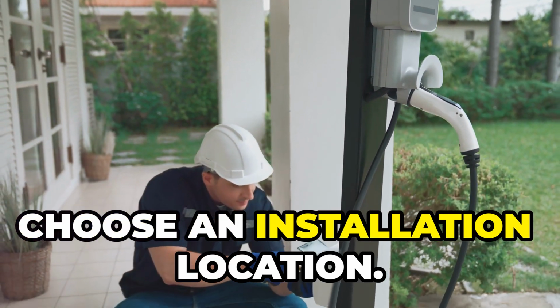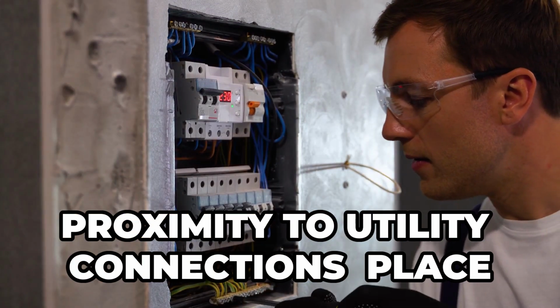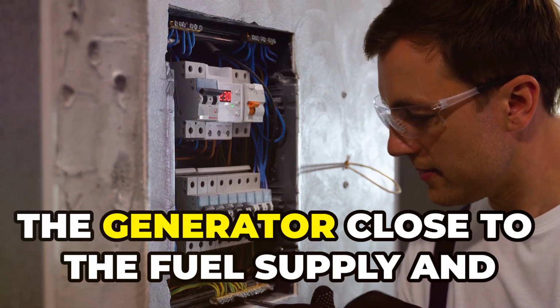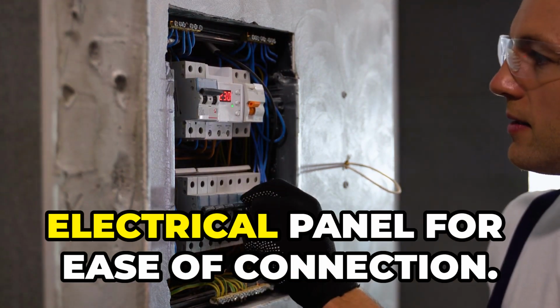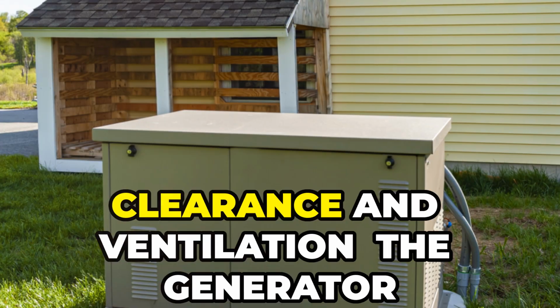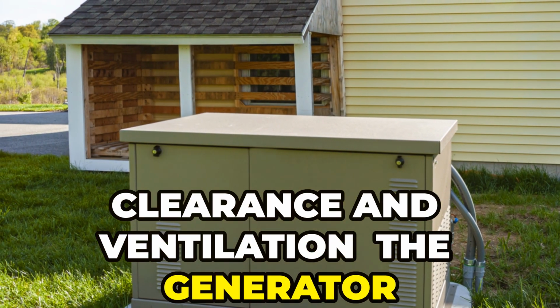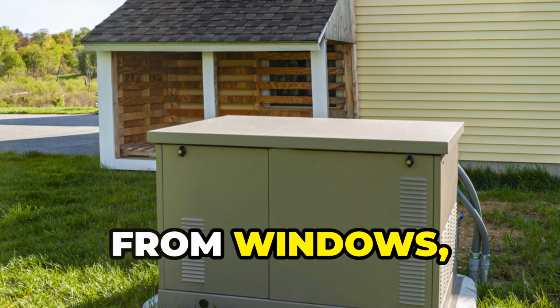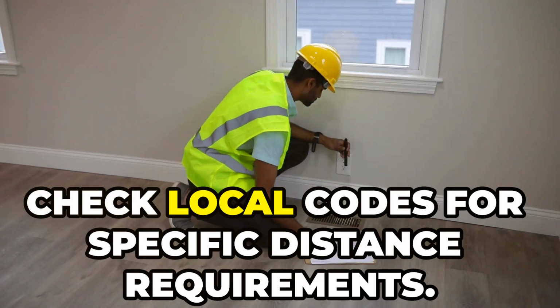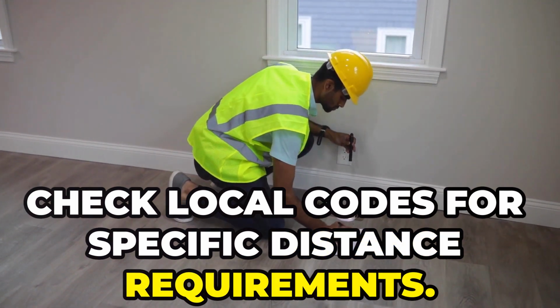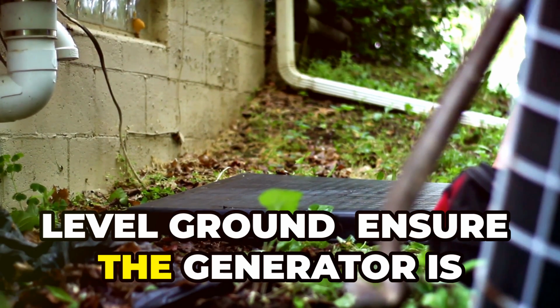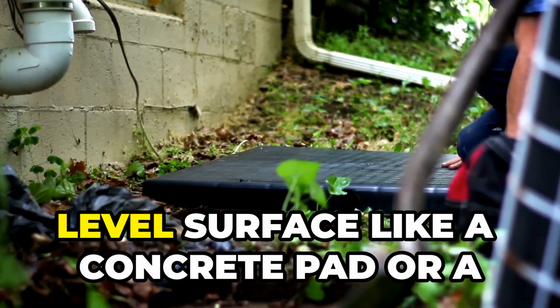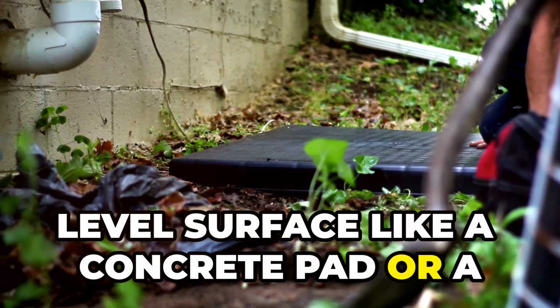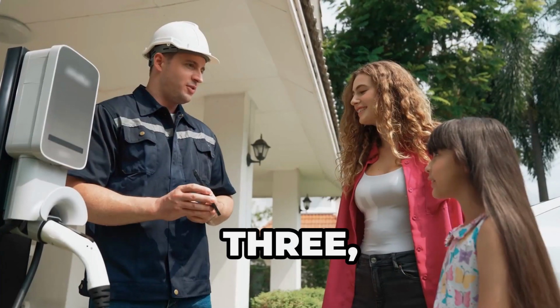2. Choose an installation location. Proximity to utility connections. Place the generator close to the fuel supply and electrical panel for ease of connection. Clearance and ventilation. The generator should be placed at least 5 feet away from windows, doors, and vents. Check local codes for specific distance requirements. Level ground. Ensure the generator is installed on a solid, level surface like a concrete pad or a prefabricated base.